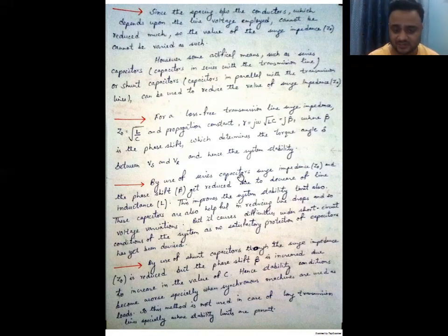By the use of a series capacitor, surge impedance and phase shift get reduced due to the decrease in line inductance. This also improves the system stability limit.